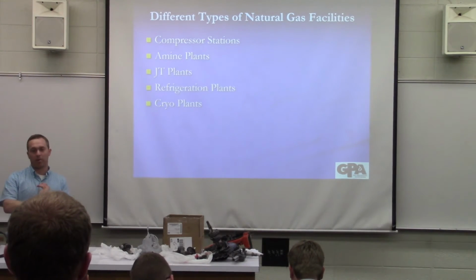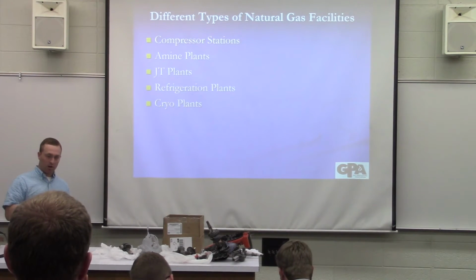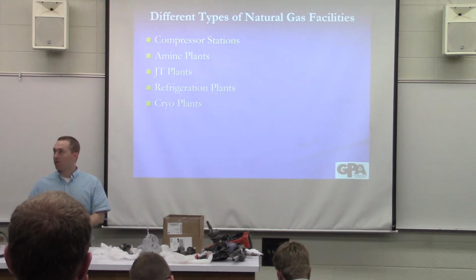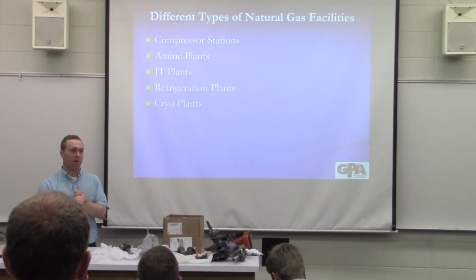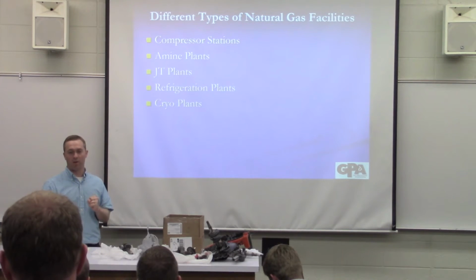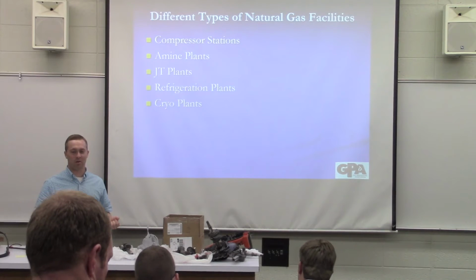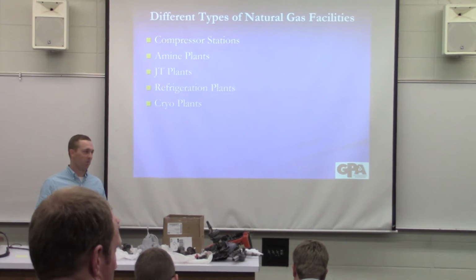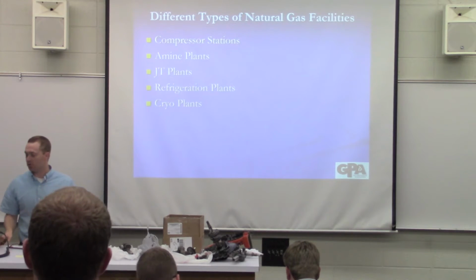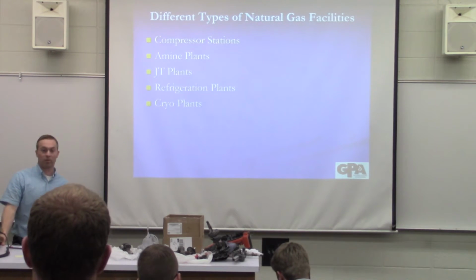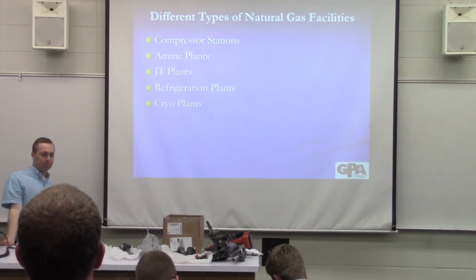So the next step up, I would say, is refrigeration plant. A refrigeration plant, we use propane refrigeration. I was prepared to maybe do a little more than what I'm going to have time to do to talk about refrigeration. But we use propane, and the reason we like to use propane is because we have it, right? That's one of the reasons: we make our own refrigerant, so it's really easy to make it up when we need to. And propane works really well as a refrigerant in natural gas processing.